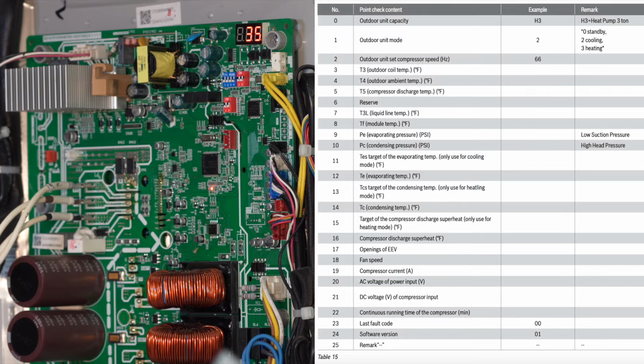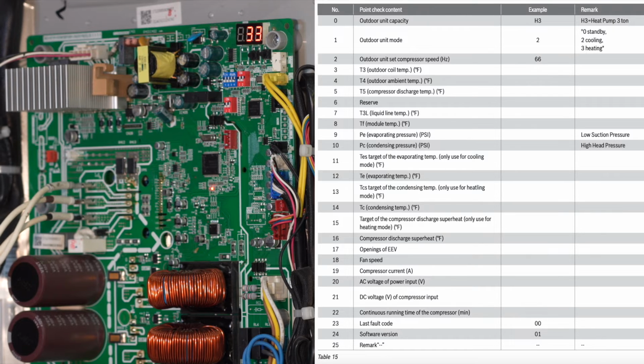Your number 17 is the positioning of your EEV. Now remember, the EEV is only used in the heat cycle. We're metering at the air handler with our TXV during the cooling cycle. We use the EEV for the heating cycle when we reverse the flow of refrigerant and we go to the heating mode. So in the cooling mode, which is what we're in right now, that EEV is going to be wide open, and we're just bypassing flowing straight through it. We're not metering at all from here until we go into the heat cycle. 18 is your fan speed. Well, because we were in the forced mode, this is an 11-speed motor, it was ramped all the way up, and that was 11. Number 19 is your compressor current. That's my amp draw. At that time, at forced mode, ramped up to 45 hertz, this thing was pulling 5 amps, ramped all the way up. Wow. Yeah.